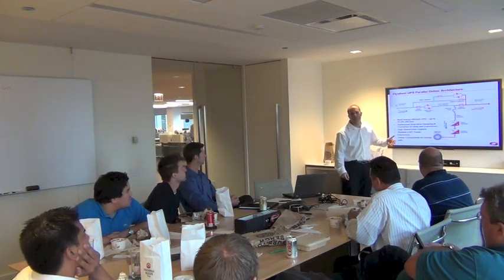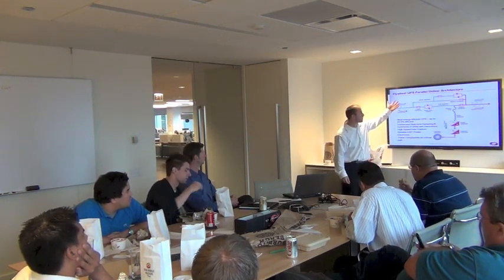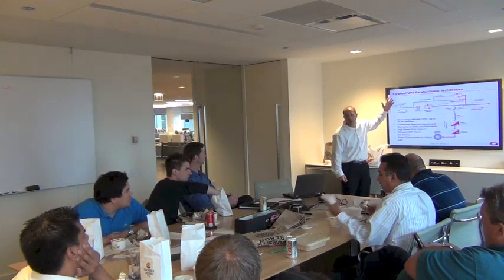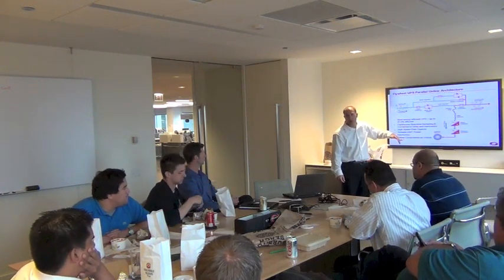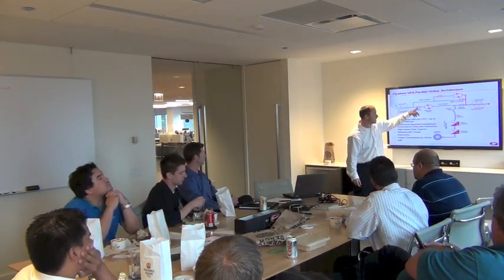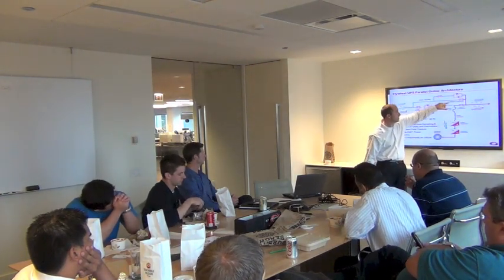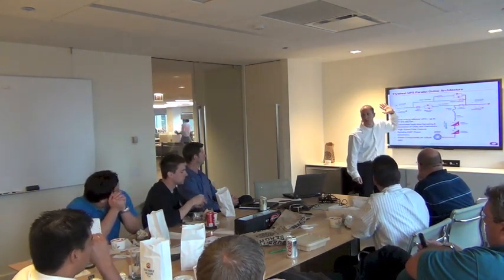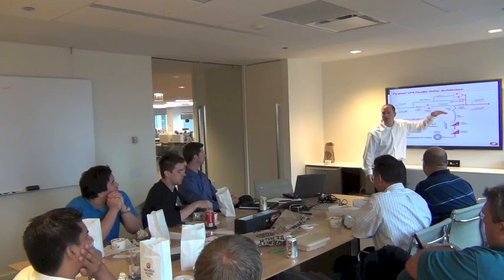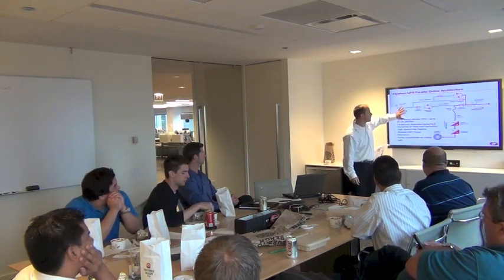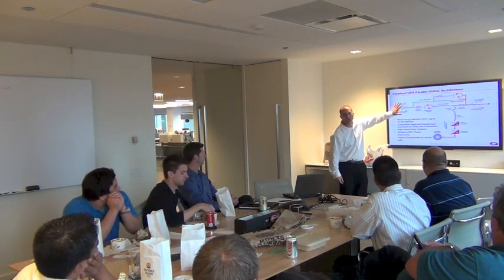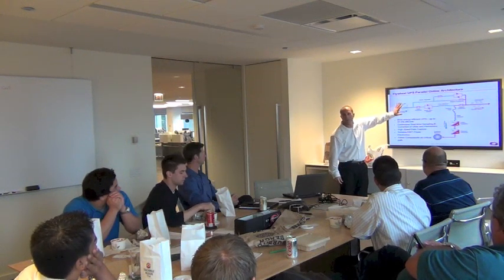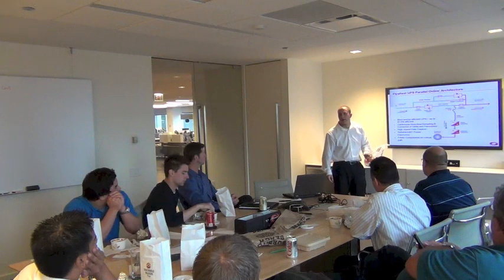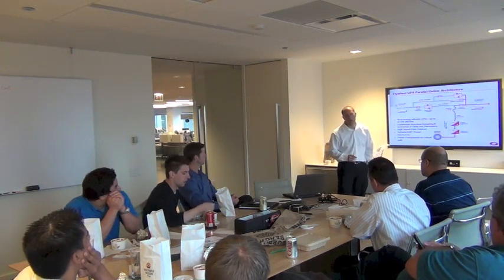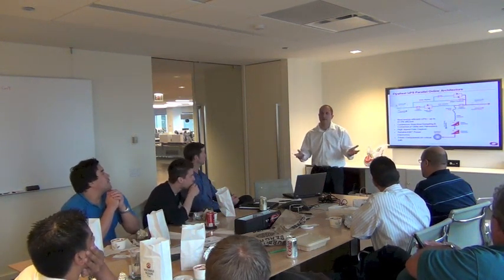So let's say we program it at plus 10, minus 10% input voltage window. If our utility falls outside of that 10% window, we're going to disconnect from the source. Input contactor's going to open, and these contactors, this one's already open, this one's going to open. So you're going to completely disconnect from the source to prevent backfeed, and you're in discharge supporting your load until that power returns, whether utility or your generator, 480 volt, 60 hertz, or wherever you are in the world, 400 volt, 50 hertz. Once you qualify that source, you'll walk the load back onto utility. So very, very similar to a traditional double conversion UPS from a continuous power sequence.